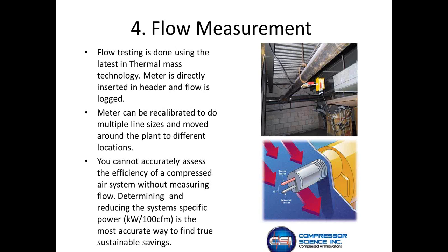You need to know what the flow is and pressure at that process. You can't accurately assess the efficiency of a compressed air system in kilowatt per 100 CFM without determining what the true power is and what the true flow is going into the facility.